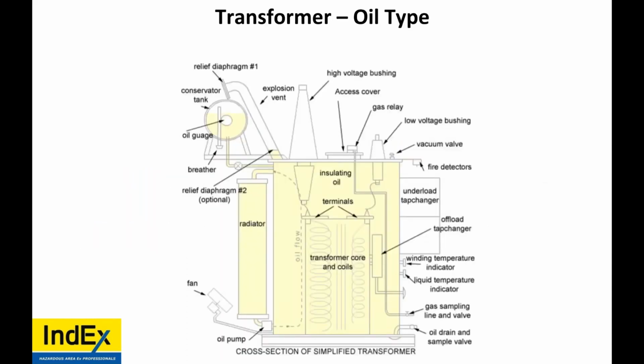When we're talking about oil-filled transformers, this is a typical non-EX oil-filled transformer. Everything inside is lubricated and cooled by the oil or liquid, and there's a radiator and a fan. Think of the engine in your vehicle, where the oil goes through an oil radiator and is cooled. There's also a reservoir of oil, a breather, and a level gauge. The HV and LV isolators, your connection points, are outside, so this would not be acceptable for hazardous areas, but it's to give you an idea. There are also oil drainage points and gas sample lines.